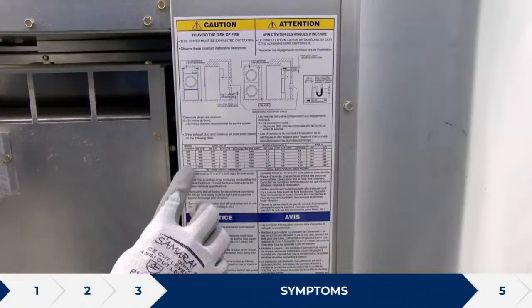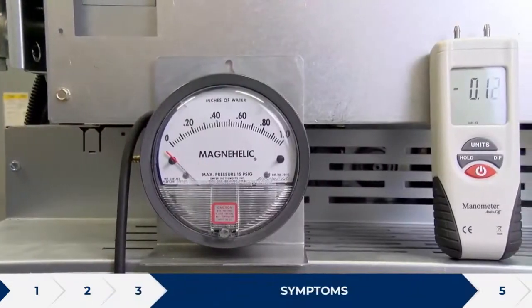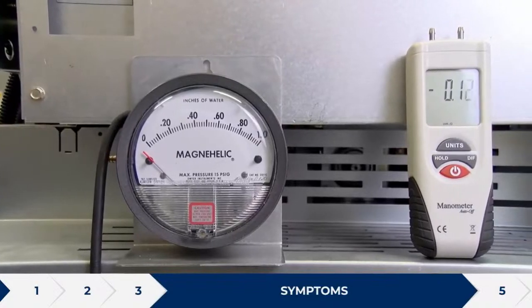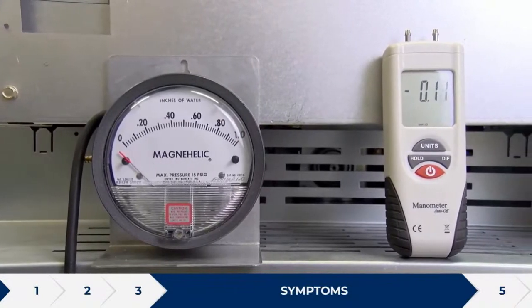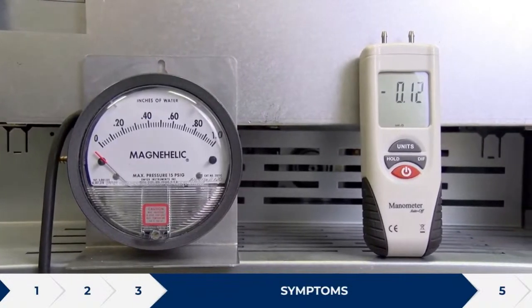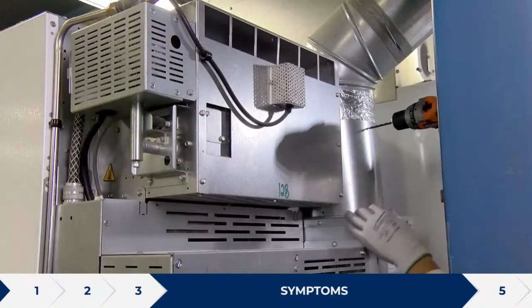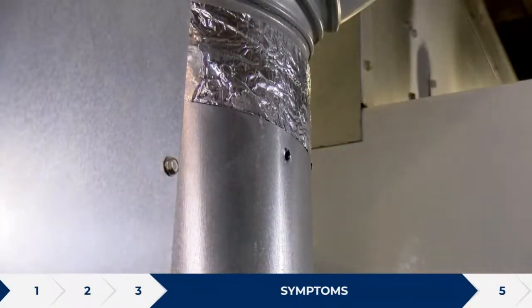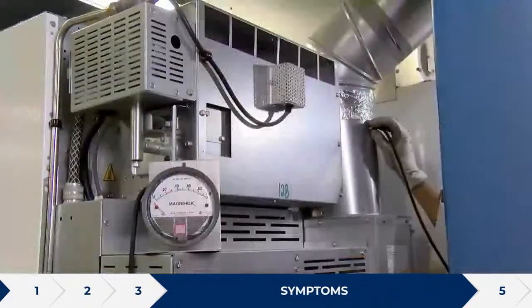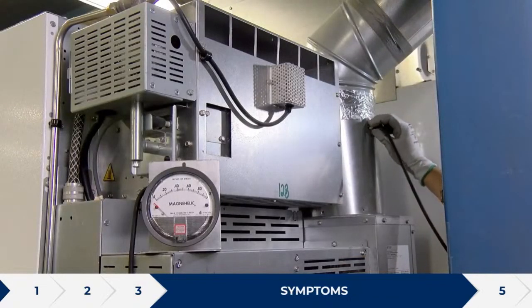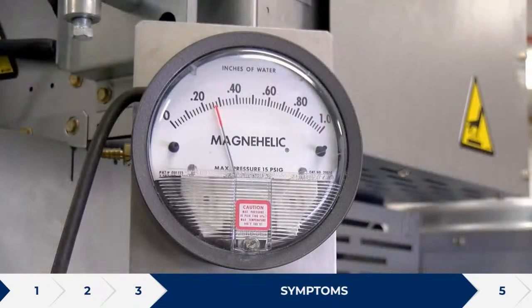When it comes to diagnosing questionable vent work, a tool called a manometer is used to see if the maximum allowable back pressure is adequate. To monitor pressure, a 1/4 inch or 6 millimeter hole must be drilled into the vent work within 24 inches or 60 centimeters from the connection point on the tumble dryer. Note, when testing on a manifold vent system, all machines on the system must be running.